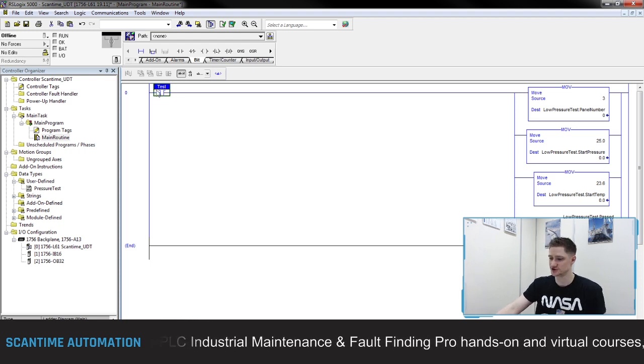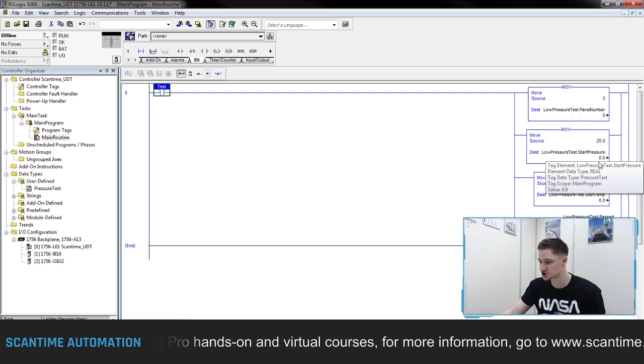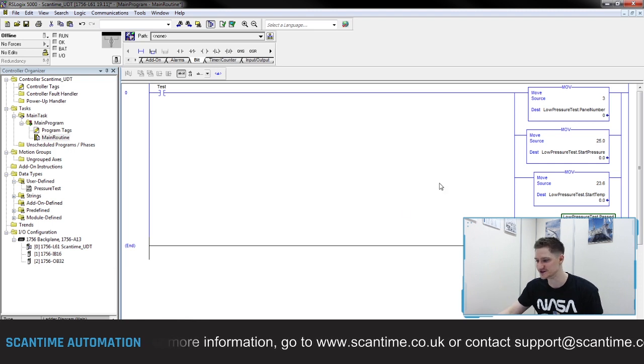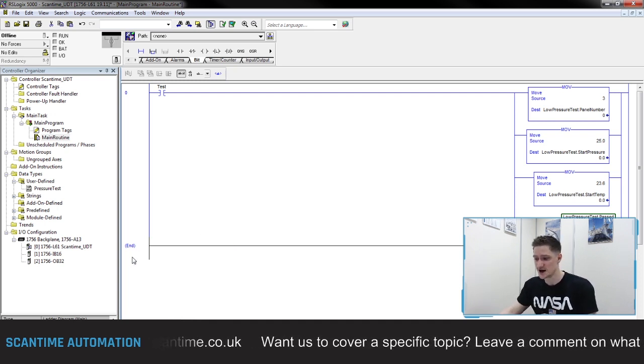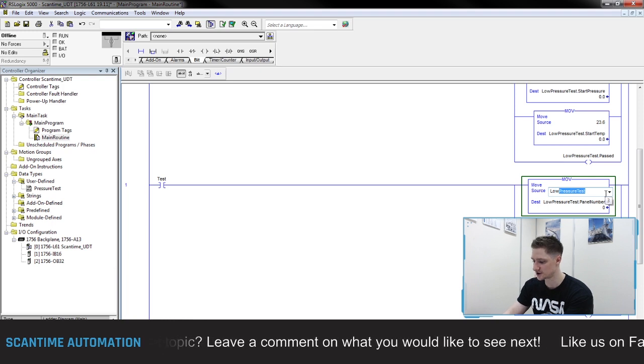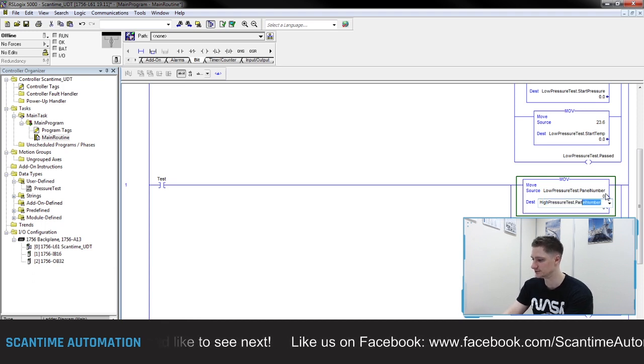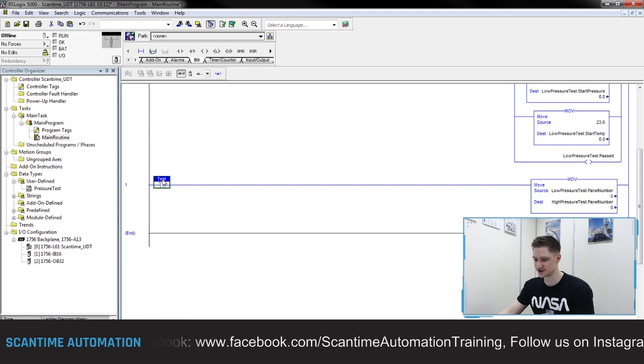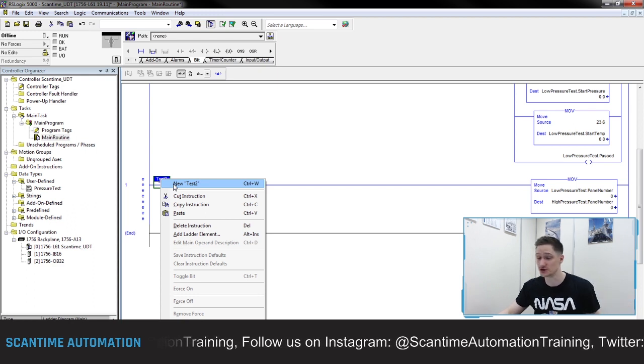I'll also turn on a bit — go to my bit folder, add in a coil, and turn on the low pressure test pass bit. So when my test bit turns on: three is moved into the panel number (integer), 25.0 and 23.6 are moved into start pressure and start temp (floating point), and I'm turning on a bit inside of that one UDT. We can also transfer data from my low pressure UDT into my high pressure UDT — sourcing low pressure test dot panel number and moving it into high pressure test dot panel number.